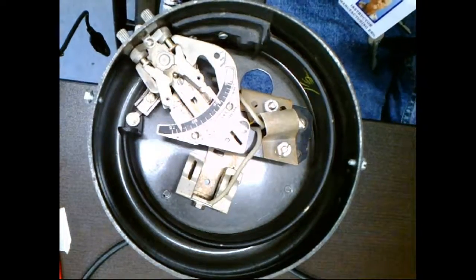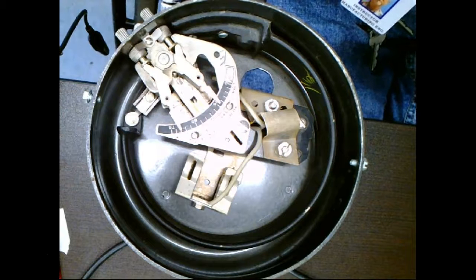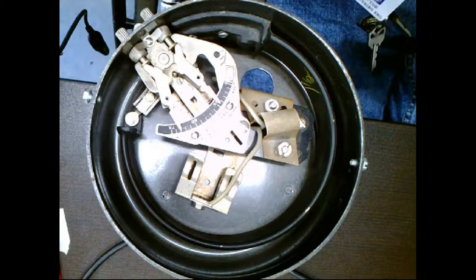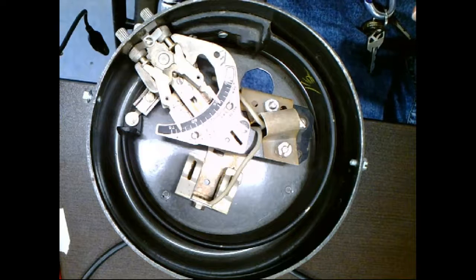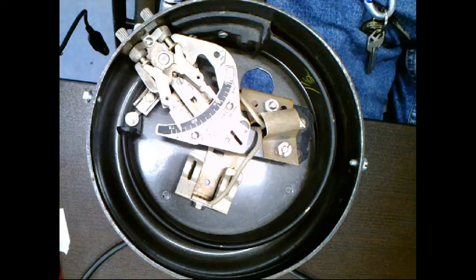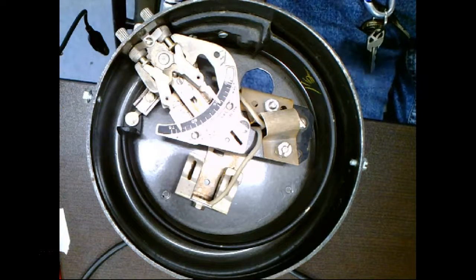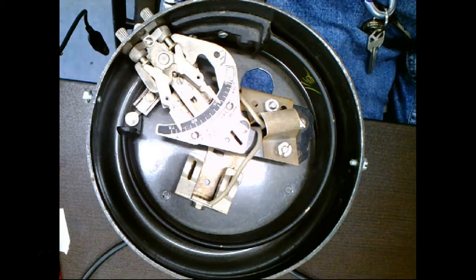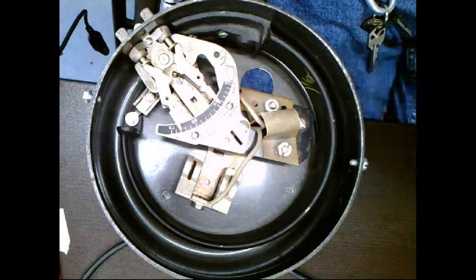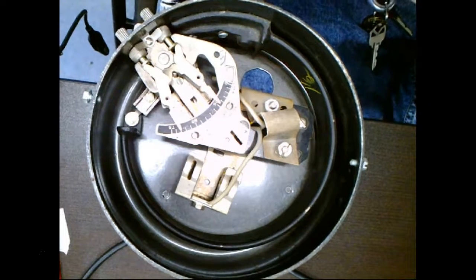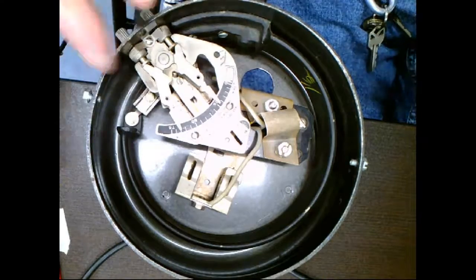Could be air, could be hydraulic, the Bourdon tube doesn't care. All the Bourdon tube does is take a pressure and convert it into a motion. That's all it does, it converts it into a motion. Now if I want to use that motion digitally, I've got to add another sensor, like a limit switch, to give me a 1 and 0 output, or a resistor.